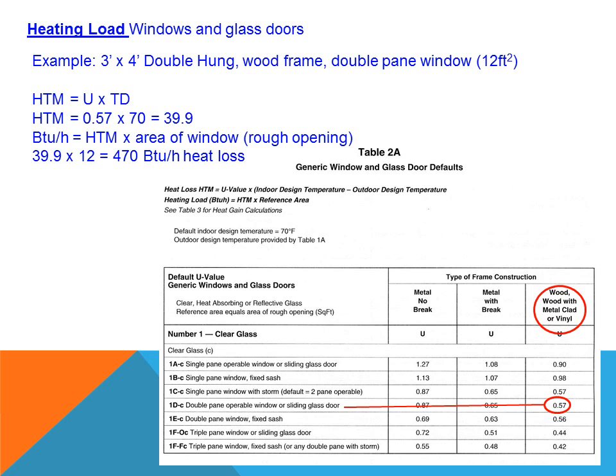Here's a heat load example for windows and glass doors. The window is 3 feet by 4 feet, double-hung, with a wood-framed double pane — 12 square feet total. The U-factor, or heat transfer factor, times the TD: 0.57 times 70 degrees equals 39.9. Multiply that by the square feet — 39.9 times 12 square feet — gives a total heat loss of 470 BTUs per hour. Looking at Table 2A row 1DC, moving over to the wood-type window, gives the heat transfer factor (U-factor) of 0.57.